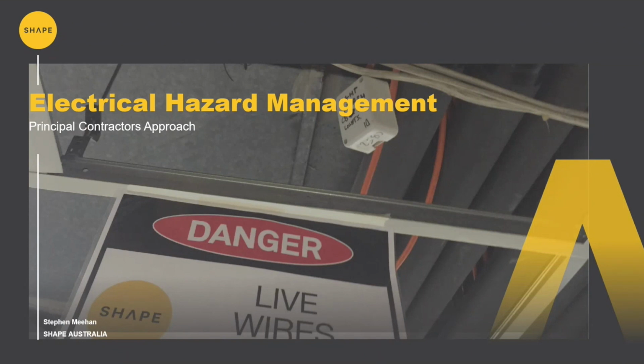So we put a lot of time and effort into the process, and it has actually significantly reduced the number of electrical related incidents that we do have within the business. Getting to the types of environments that we often work in where the hazards are greater than others, older buildings such as hospitals, medical facilities, universities, education facilities often have the hidden risks of unsafe electrical wiring, unsafe electrical switchboards, not in the sense that they're unsafe in their current configurations, but when you start opening up buildings to do refurbishment works, you'll often find that the wiring can be unsafe.